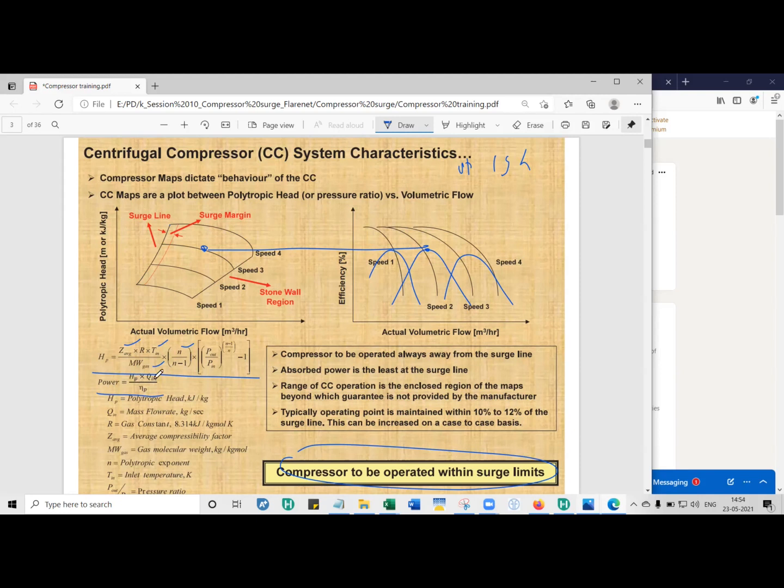So from this, what we can understand is, so the amount of power that is required to compress a gas from an initial pressure to the final pressure is the polytropic head into the mass flow rate divided by the polytropic efficiency. So this is an easy expression, at least to me because I use that because polytropic head is kilojoule per kg, and flow rate is kg per second. So when the kgs get cancelled in numerator and denominator, you get. So what we can understand is the more the polytropic for a given mass flow rate, as the polytropic head increases, you need more power to compress the gas.